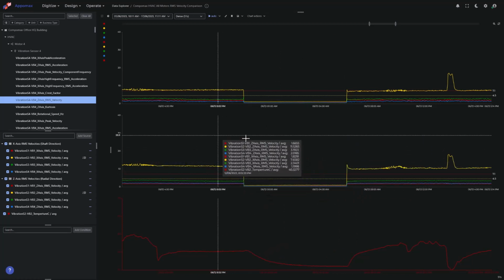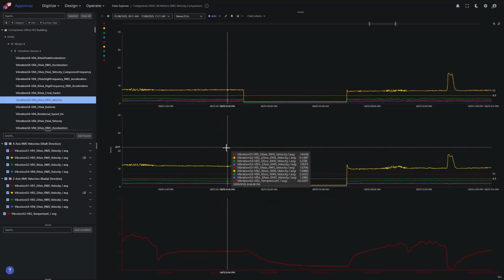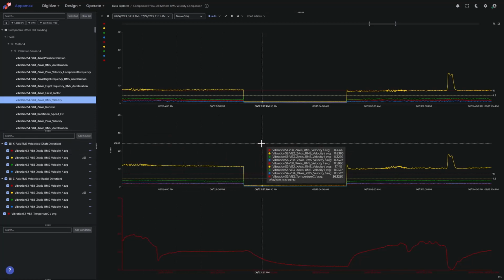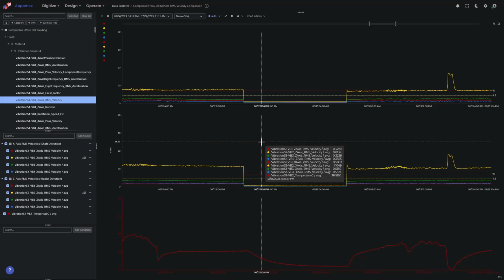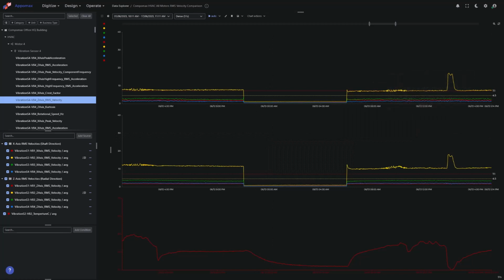And this is looking at only one parameter of the vibration sensor, the RMS velocity. To consider the bearing, we have to go into the range of acceleration at a higher frequency, and much more understanding is needed to figure out how to set alarms and events so that we are detecting an onset or trending of the error.